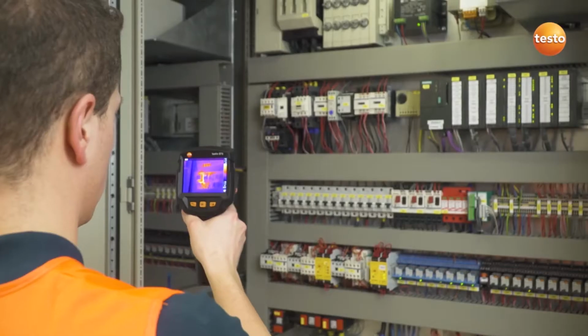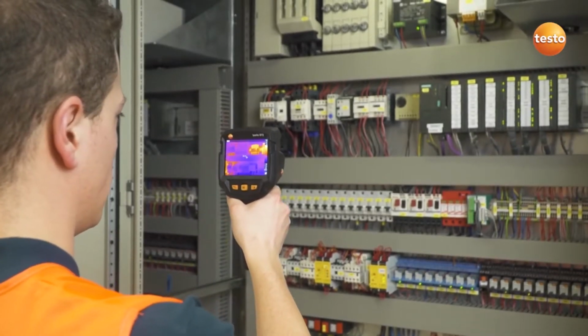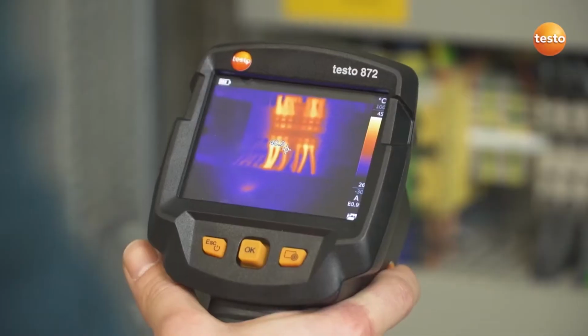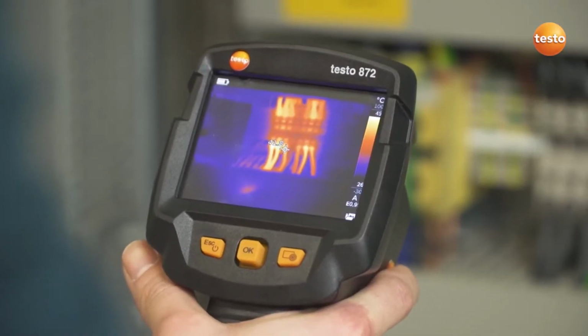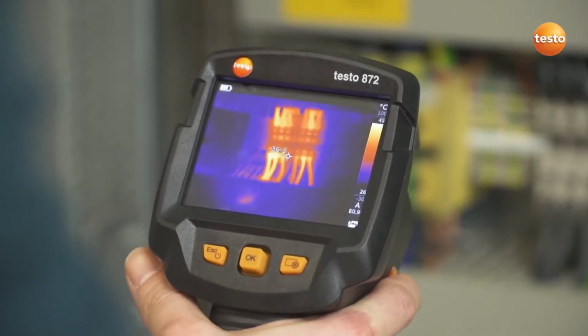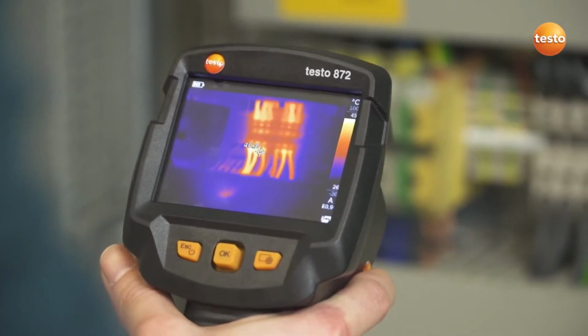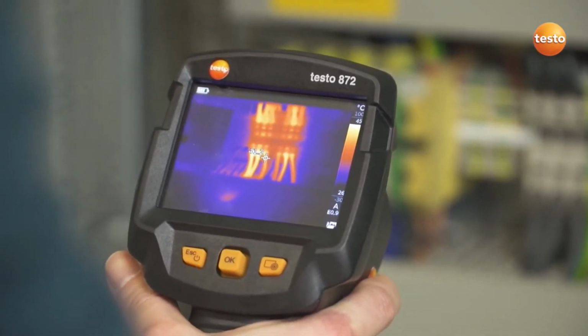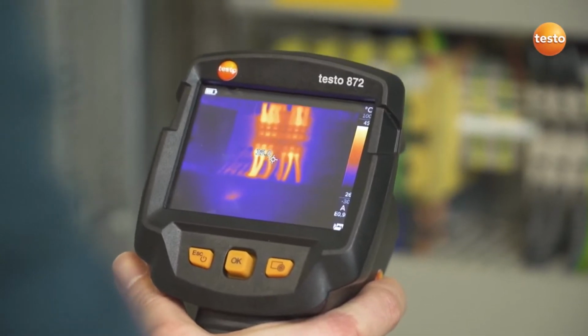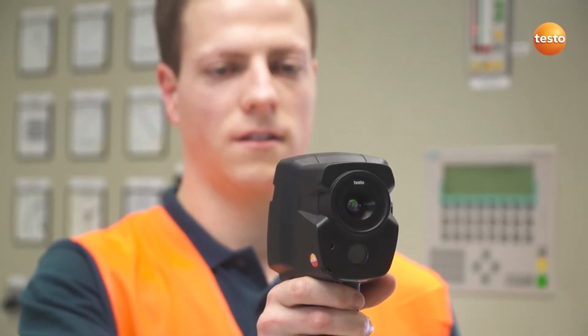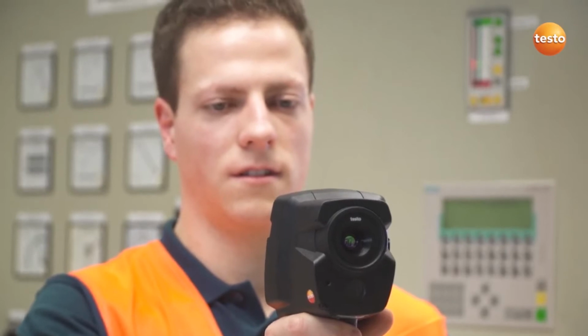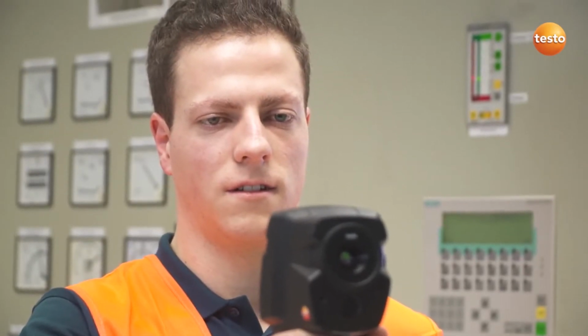Everything's fine. In the switching cabinet, we're looking for overheated components. They are often very small. That's when the IFOV warner can be very useful. It visualizes which measurement object can be measured from which distance and shows you whether the temperatures of surrounding objects might falsify the temperature of the actual measurement object.